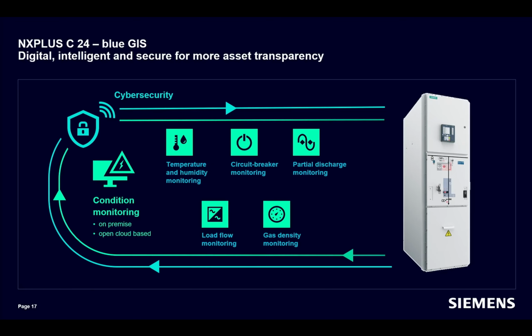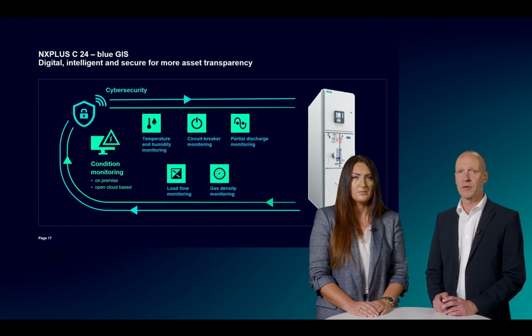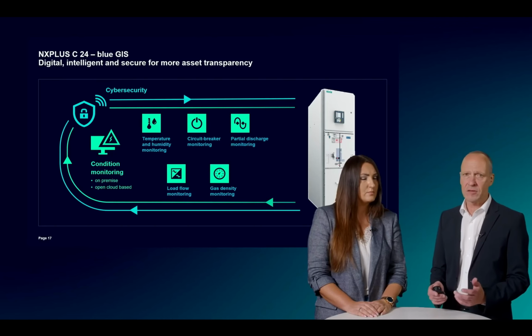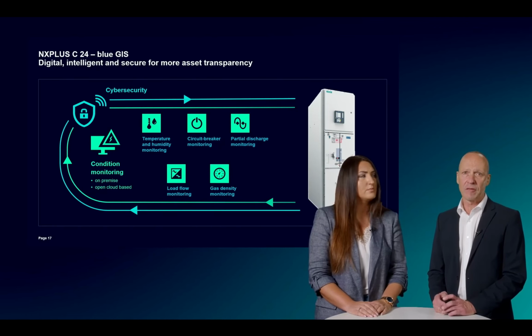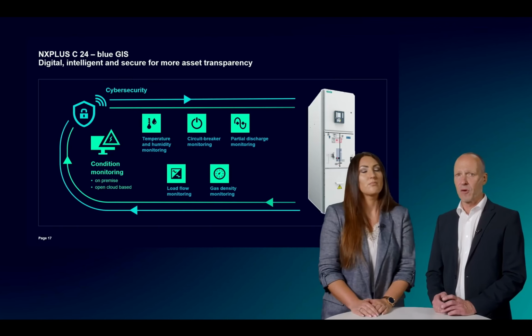Electrical insulation can become damaged over the time due to faulty or incorrectly installed components on our switchgear. As a consequence, partial discharges may occur. Our partial discharge monitoring system provides an early warning, allowing to prevent failures and damages on the switchgear. Gas density monitoring reports a warning in the very unlikely event of a gas loss. And last but not least, current and voltage transformers connected to an intelligent short circuit and earth fault indicator, like our SICAM FCM Plus or protection relay from our SIPROTEC 5 family, can monitor the load flow.